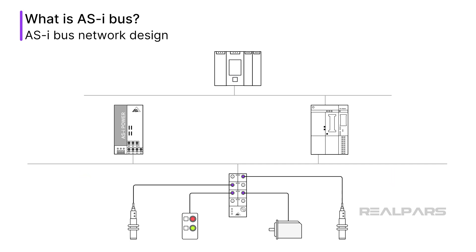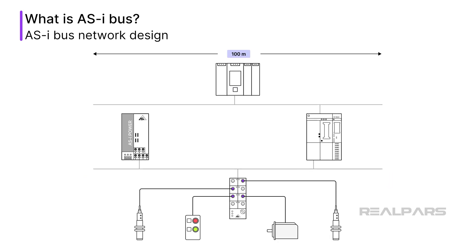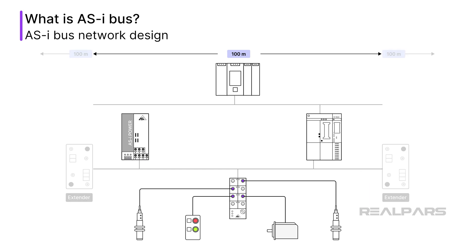A single AS-i segment may run up to 100 meters. Drops of up to 3 meters from the segment trunk cable are allowed. Longer drop lengths may introduce excess voltage drops and data errors. Segment lengths of up to 300 meters are possible using segment extenders, a more advanced concept.